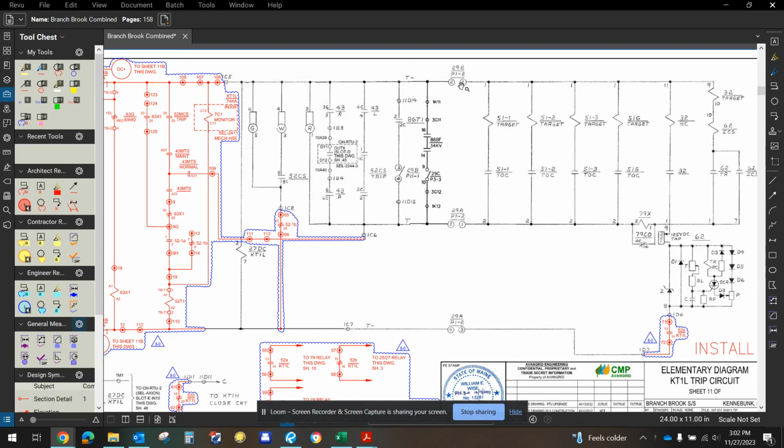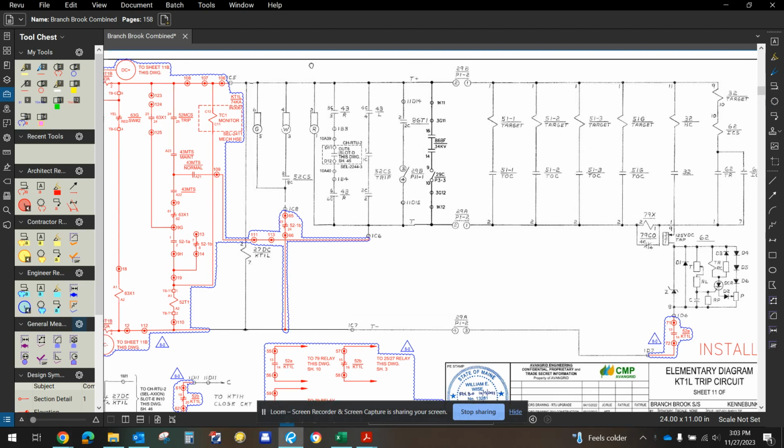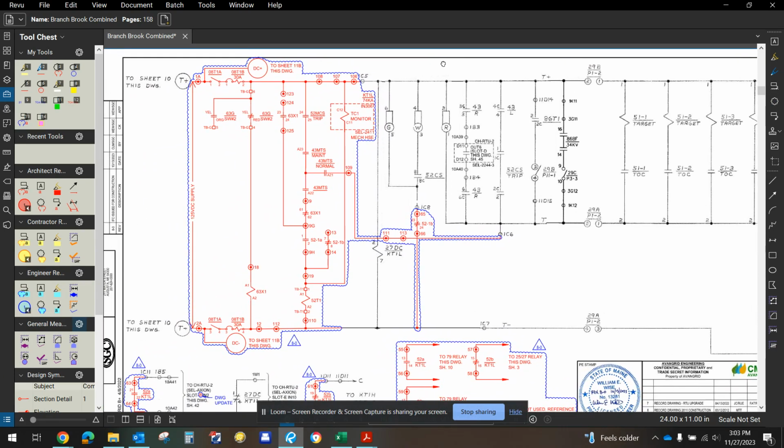And on the last video, we looked at how this point, 29B P12, is connected to this circuit. It's actually connected from here to 9 to 11 and all the way down. So it's physically wired differently than it's drawn, but it works electrically the same, because they're all landed on the positive rail, and we already talked about that. So when we digest drawings, we are looking at what is actually happening here. This is something that you have to understand.